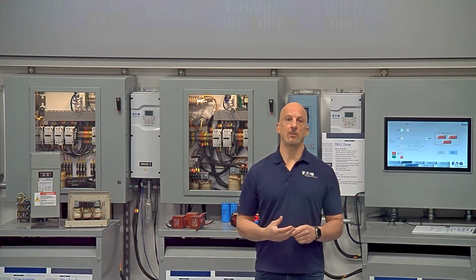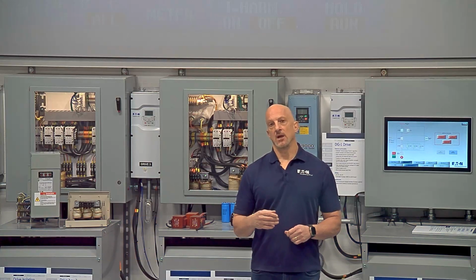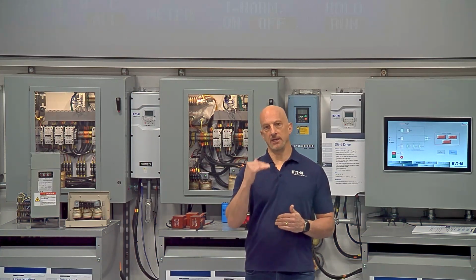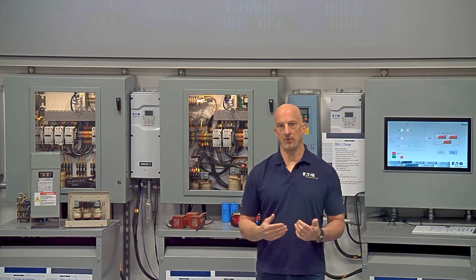So this is probably one of the most frequently asked questions when you're talking about active harmonic filters, and that is, why do you need a line reactor in front of the active filter, and why does my harmonic current increase out of my loads when I add an active harmonic filter?